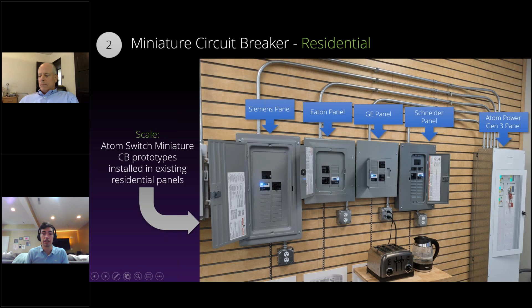Yes. As for cybersecurity, I know that's a huge topic. I'm not on the team developing the cybersecurity, but I know they're taking it very seriously. As for controlling the breaker like you would today, yes you can. There's still a mechanical device here that you can open up. If you're doing any work on the other side of the breaker, we don't recommend using the solid state as the off switch. We always say you should air gap before doing any work downstream, the same way you'd lock out and tag out in a commercial setting.